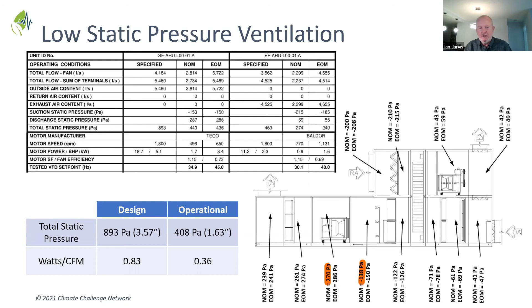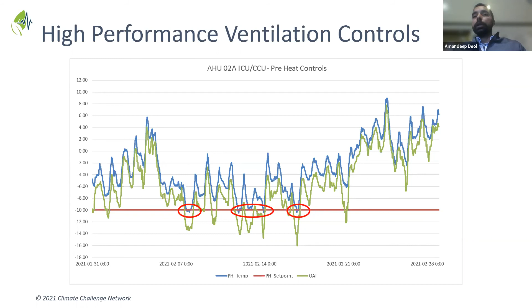Yeah. So this is just a graphical analysis of how the heat wheel operates in this building. What you see in the red line is the set point. It is minus 10 degrees C. Your green line is your outside air temperature, and your blue is your preheat temperature. The graph is telling you, as you see in the circles, that the preheat is trying to maintain minus 10 degrees C going into the wheel. As the outside air temperature drops below minus 10, the preheat comes on and keeps the set point at minus 10. Keeping the preheat temperature at such a low temperature helps you maximize the thermal wheel efficiencies and the operation of the thermal wheel, which is what you're seeing in the results of the lower gas use in the heating season in this hospital.